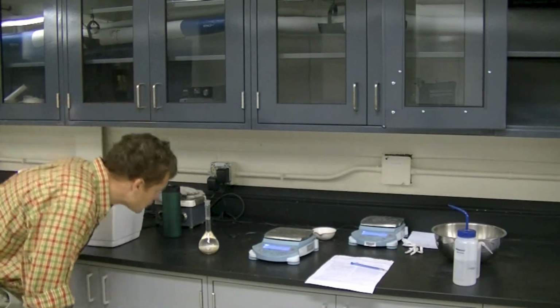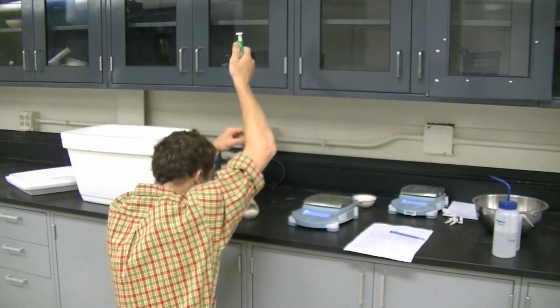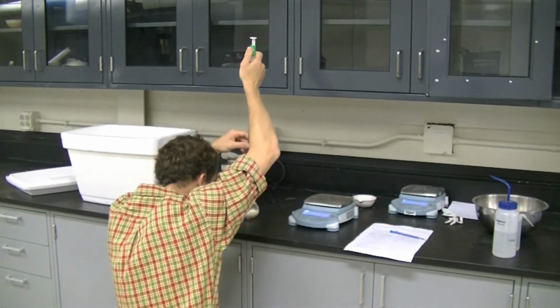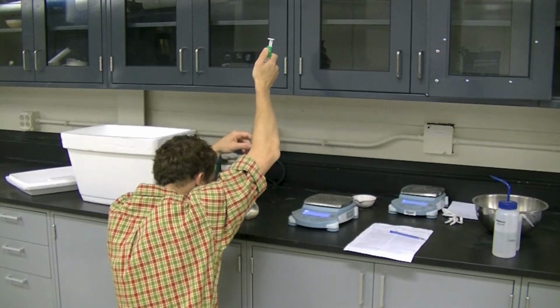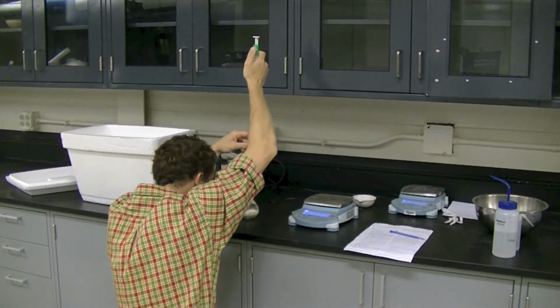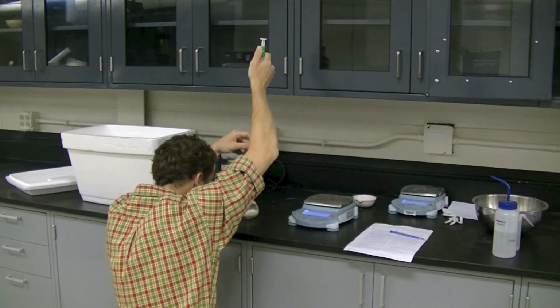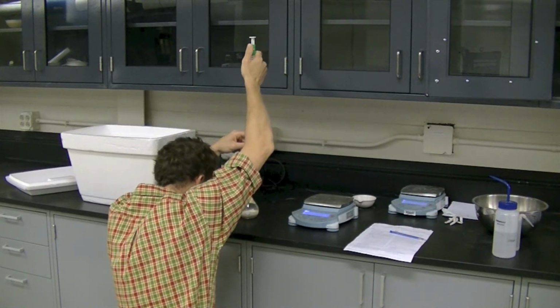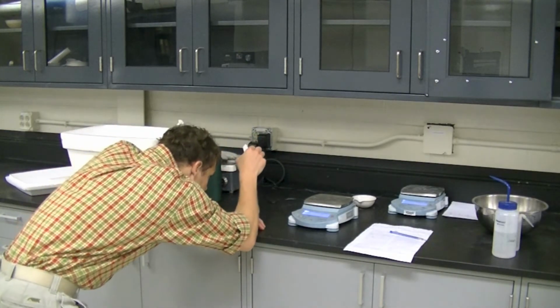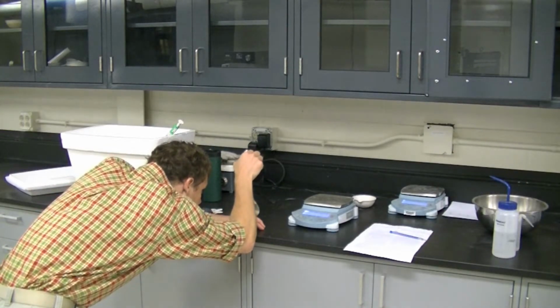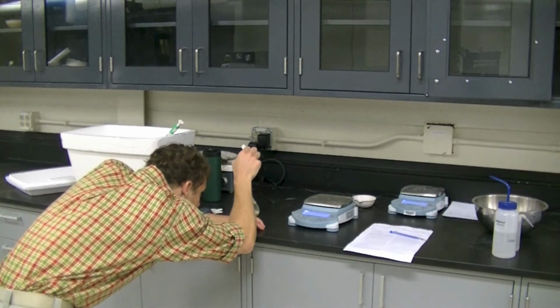Adjust the water level up to the calibration mark, using the same tip insertion method as described. Use the de-aired water from the container. Adjust the water level so that the bottom of the meniscus is at the mark. If water is to be removed, use a paper towel. Be sure that the inner portion of the flask above the calibration mark is dry, as well as the outside.